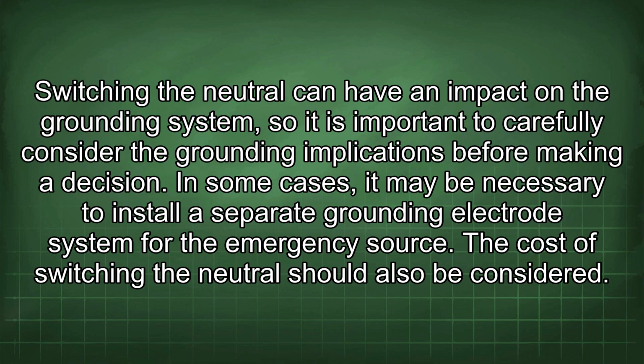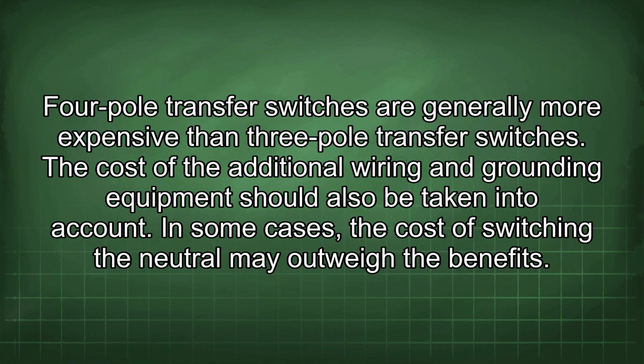The cost of switching the neutral should also be considered. 4-pole transfer switches are generally more expensive than 3-pole transfer switches. The cost of the additional wiring and grounding equipment should also be taken into account. In some cases, the cost of switching the neutral may outweigh the benefit.